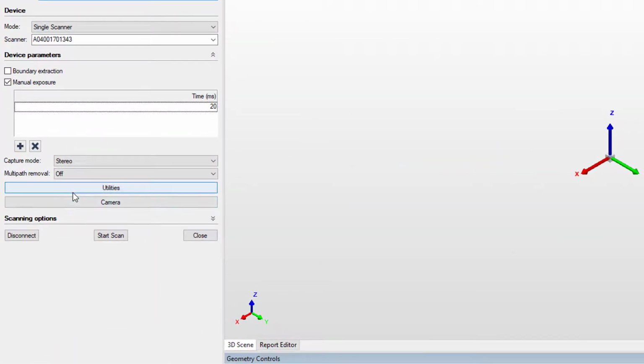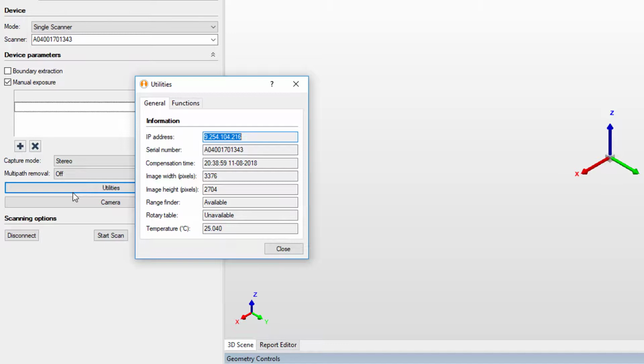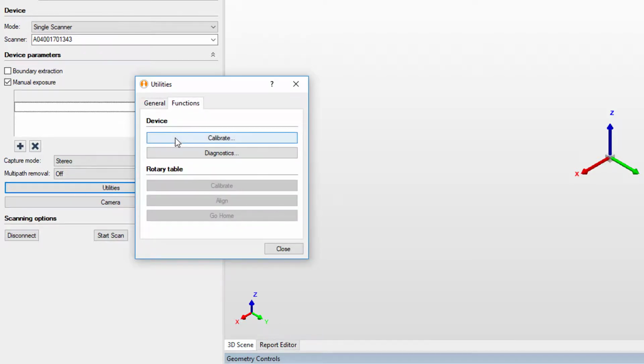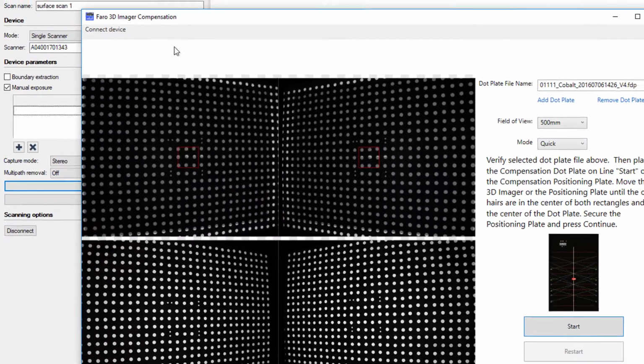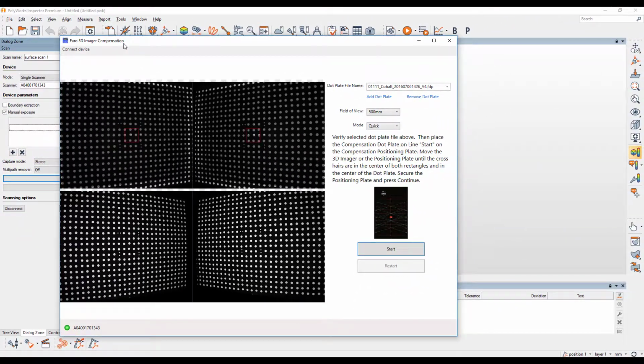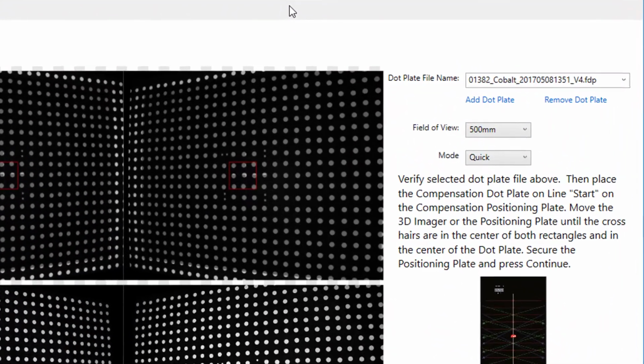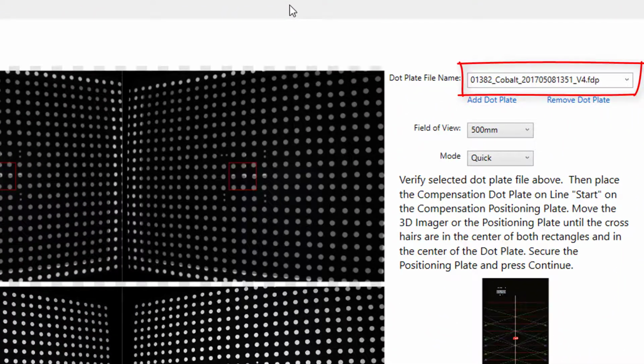Next, click Utilities in the Cobalt dialog window. Once the Utilities dialog appears, click Functions followed by Calibrate. This will open the Cobalt compensation routine. Ensure the correct dot plate file is selected. The number seen in the compensation window should match the serial number on the back of the dot plate. If the dot plate file is incorrect, click Add Dot Plate to navigate to the correct location and select the most recent FDP file for the respective dot plate.